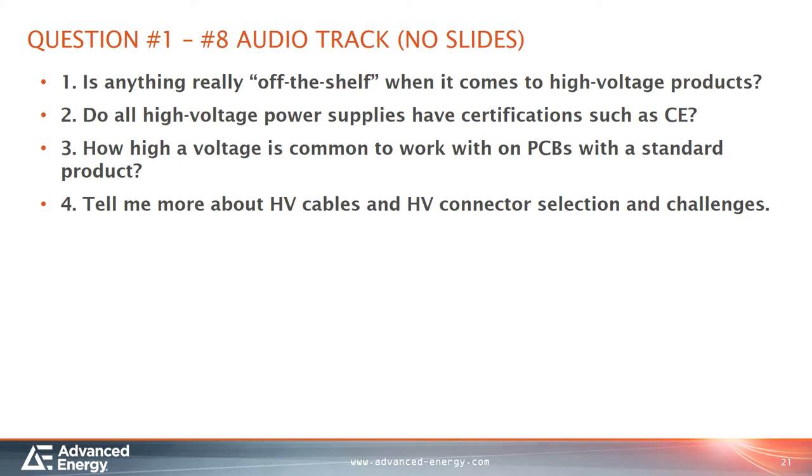The silicone insulated, of course, is not shielded. You'll get a little bit of a field effect off the wire inside the center conductor. And the semiconductor over the center conductor eliminates that field effect, so the wire is more reliable, less chance of a point source of energy coming off of the wire and damaging the insulation, less of a signature, less field stress. And the silicone wire with the semiconductor coating on the outside, followed by a foil wrap or a braid, of course, has the most uniform field because the semiconductor has this uniform field by the coating, and the outer shield has a uniform field because of the coating.